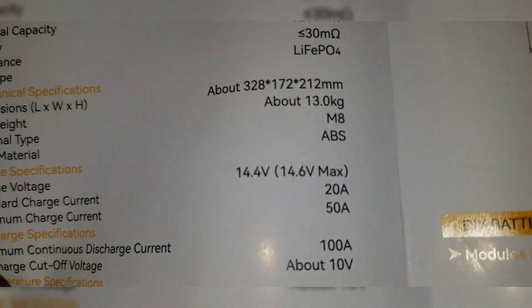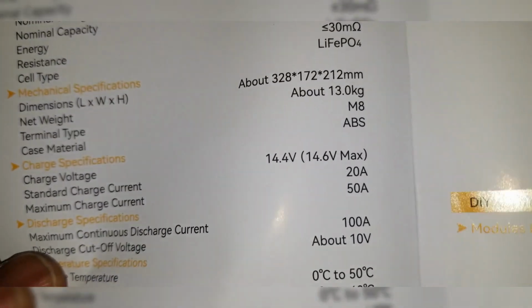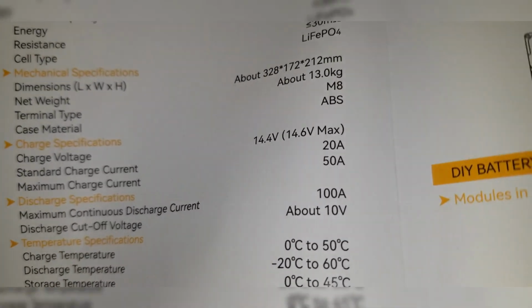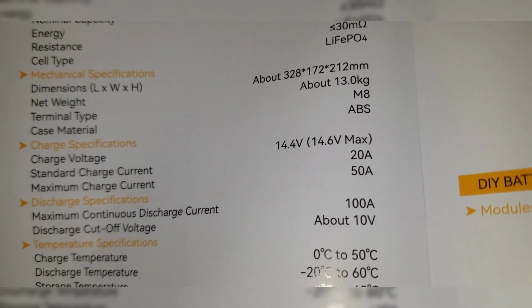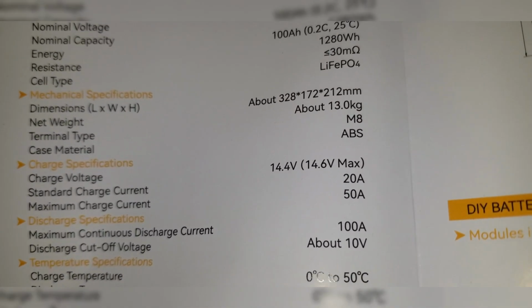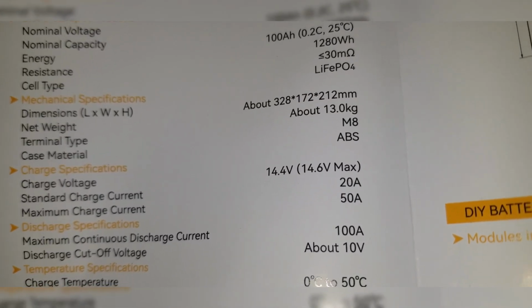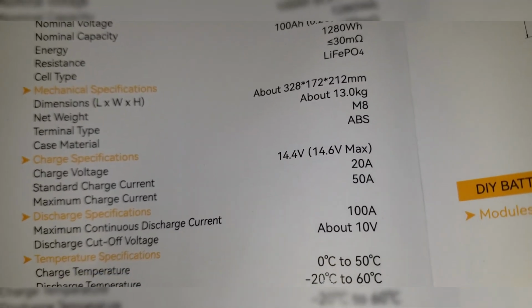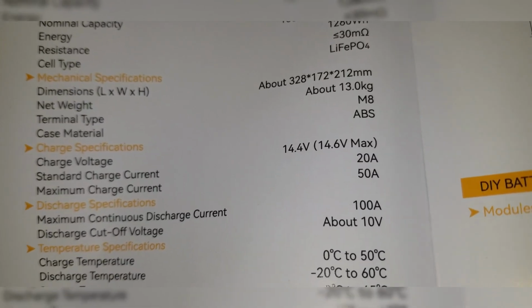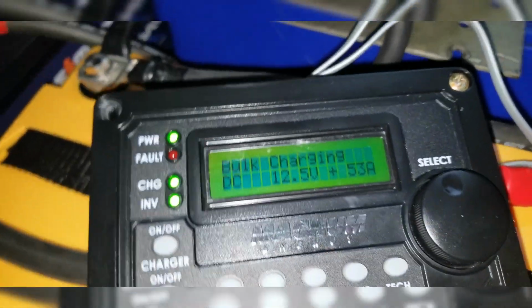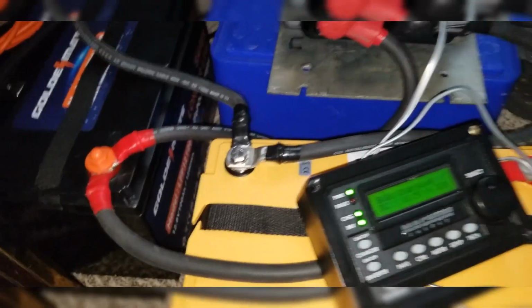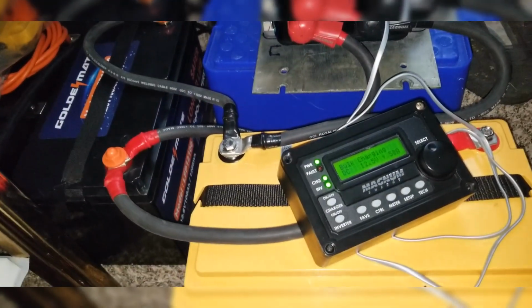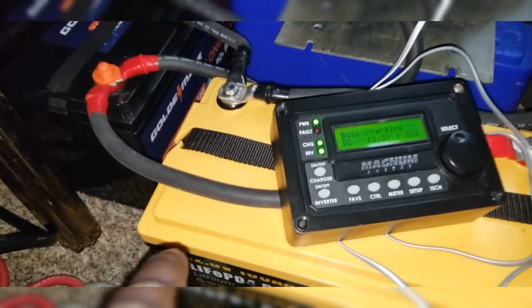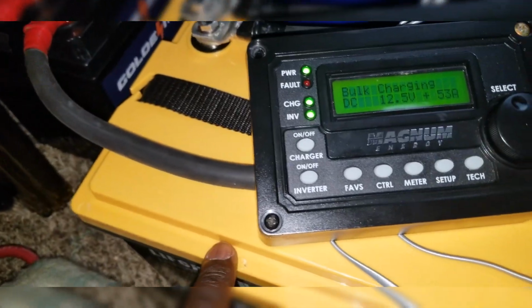See that, at 14.4 or 14.6, and it says charging voltage, see that? And they say charging current is 20 amps and the max is 50. So I decided to set this guy at 50, because these two batteries are sharing together, and instead of putting 50 amps on each battery, it's gonna cut it in half.